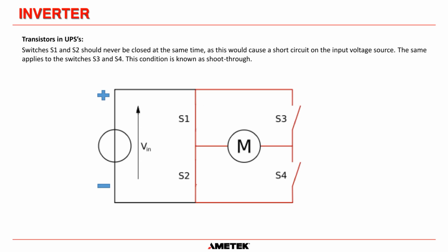One important thing to remember is that this is called an H bridge because it is shaped pretty much like an H. On an H bridge, if you close S1 and S2 at the same time, that is called shoot through. It's something that you should never ever do. And in truth, on all processor controlled inverters, it should never allow this to happen. But if it does, then that's a direct short across the positive and negative of the DC input, which is usually a battery. And that's going to cause high current to flow and basically damage. If this was an IGBT, it would seriously damage that IGBT and cause failure.